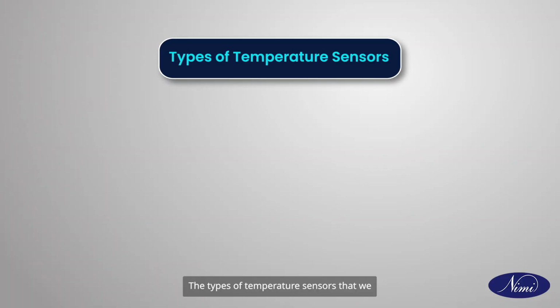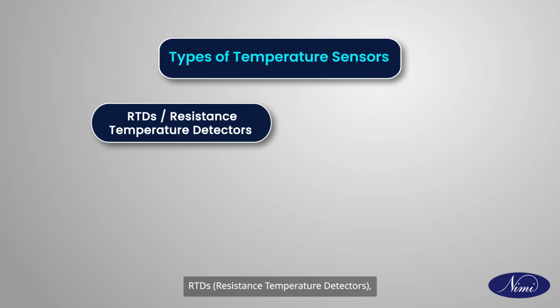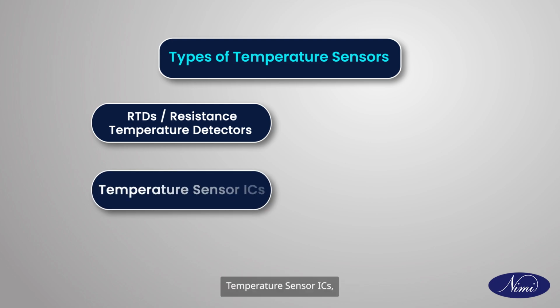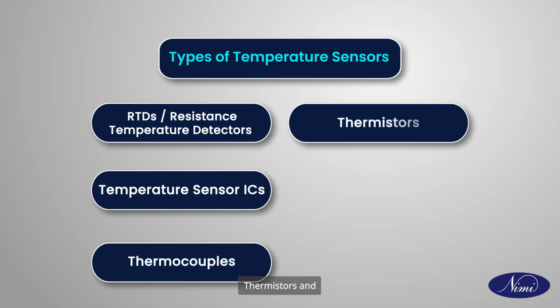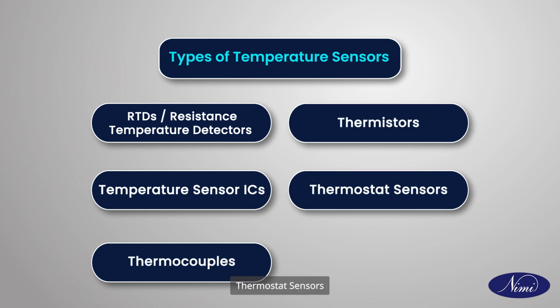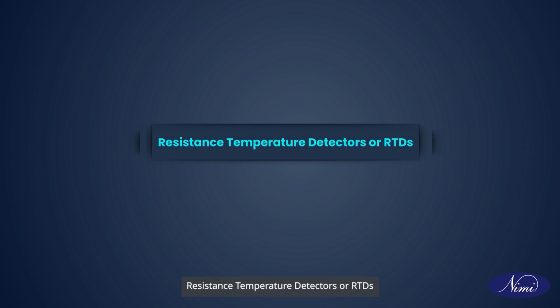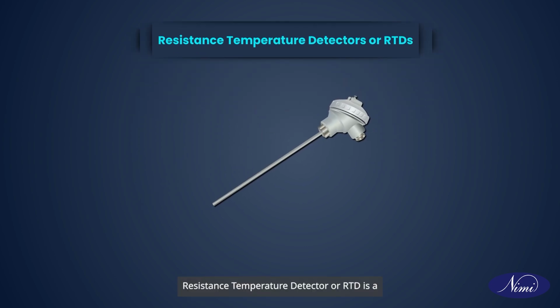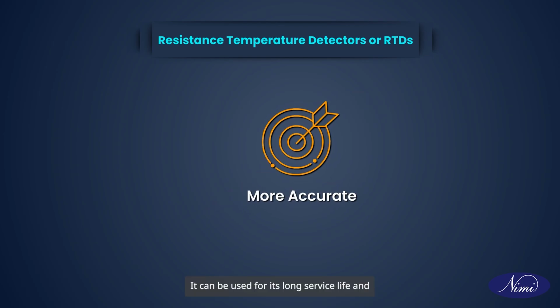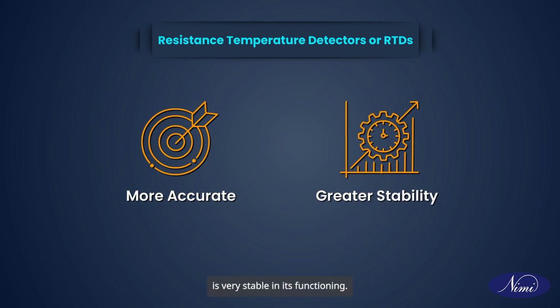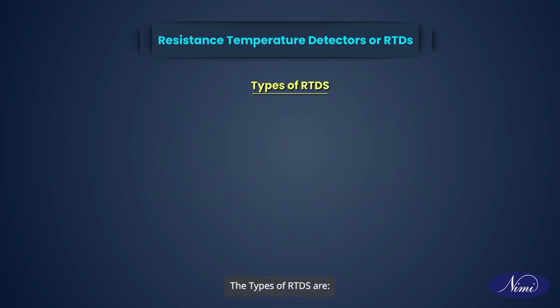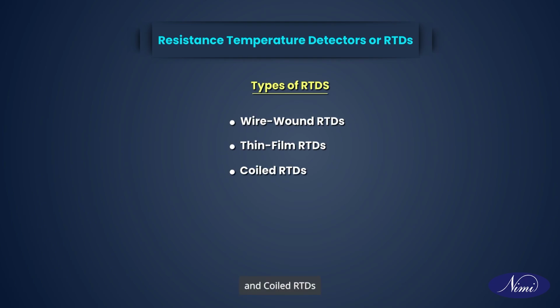The types of temperature sensors that we will look into are RTDs or resistance temperature detectors, temperature sensor ICs, thermocouples, thermistors, and thermostat sensors. Resistance temperature detectors or RTDs. A resistance temperature detector, or RTD, is a type of sensor that measures temperature by changes in electrical resistance. This sensor is known for its high accuracy. It is valued for its long service life and is very stable in its functioning. The types of RTDs are wire wound RTDs, thin film RTDs, and coiled RTDs.